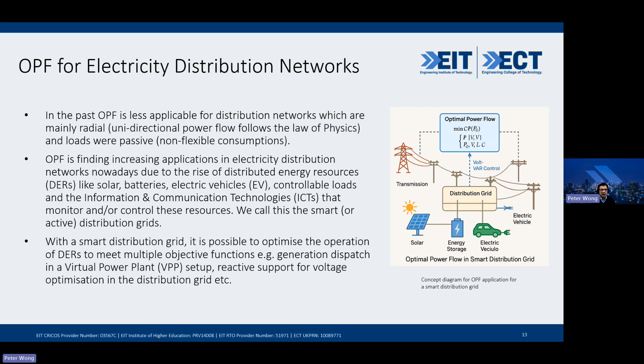So what are the use cases? The first one is voltage regulation. The goal of OPF is to maintain the voltage within acceptable limits, for example plus or minus 6% of your nominal voltage, depending on what it is. The OPF use case here is to coordinate tap changers, capacitor banks, and DER reactive control to regulate the voltage on the network. So you're running power flow, but trying to maximize your voltage to get the best voltage profile across the network.